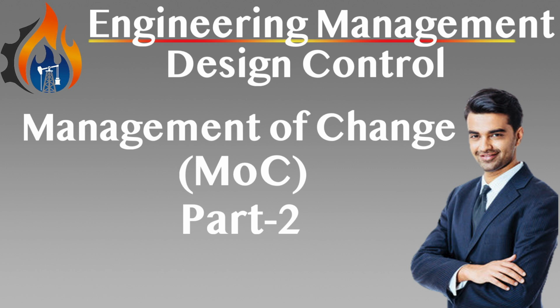Field Implementation Interface. For site work, the IETA ensures proper pre-commissioning, loop checks, insulation tests, and functional verification. Safe isolation, energization, and lockout-tagout procedures are in place, and the work is executed by qualified personnel in accordance with electrical safety standards. Through their oversight, the IETA ensures that modifications enhance, rather than erode, the reliability, functionality, and safety of the control and power systems that underpin the facility.